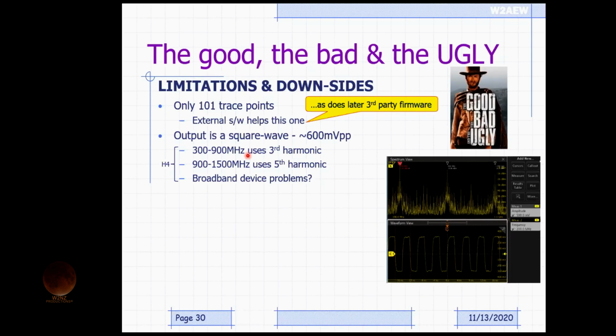Now the output of the NanoVNA is not a sine wave, right? It's a square wave. And this is actually what it looks like on a scope. There's a square wave. On the H4, for example, it uses the fundamental, and this is the square wave in the time domain, and this is what that signal looks like in the frequency domain up here. This is the spectrum plot of it. So my fundamental, third harmonic, and fifth harmonic. So on the NanoVNA H and H4, the measuring signals up to 300 megahertz use the fundamental of the square wave. But when you make measurements from 300 meg to 900 meg, it uses the third harmonic of this square wave.